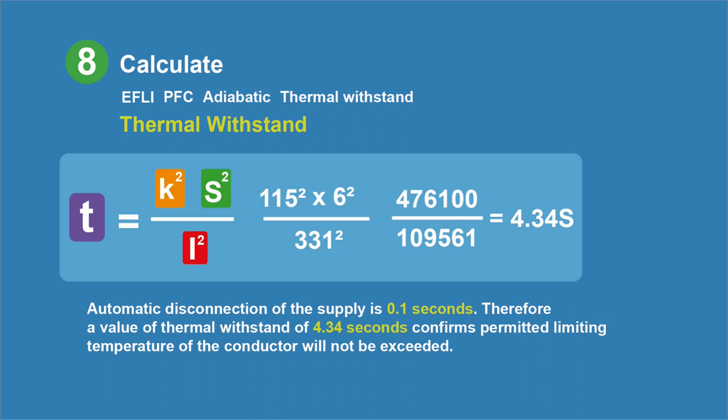Next we consider thermal withstand — this time checking that our live conductors are suitable. If there's a fault, we want to ensure the cable can handle it and the permitted limiting temperature of the conductor will not be exceeded. It's a rearrangement of the adiabatic equation. Using K for the conductor, the size of the live conductors (6mm²), and the fault current — all squared — the calculation gives a thermal withstand time of 4.34 seconds. Since we know automatic disconnection of the supply will occur in 0.1 seconds, the thermal withstand of 4.34 seconds confirms that the permitted limiting temperature of the conductor will not be exceeded during the fault.